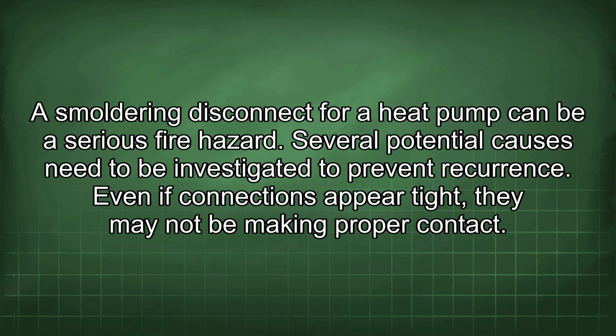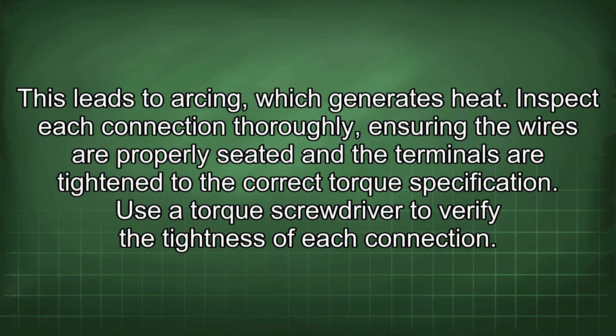A smoldering disconnect for a heat pump can be a serious fire hazard. Several potential causes need to be investigated to prevent recurrence. Even if connections appear tight, they may not be making proper contact. This leads to arcing, which generates heat.